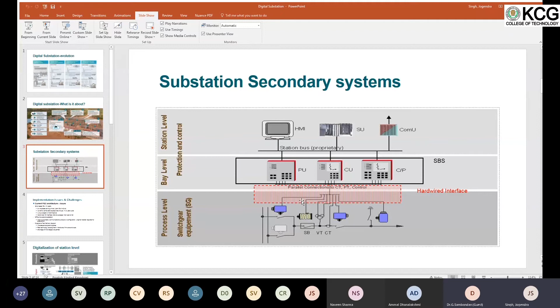No, it can be converted like this. If you see this example, the substation secondary system can be converted using a merging unit, like a merge switch box. You convert all the old CTs and wiring, install a merging unit or transducer on the wiring, and the merging unit will convert the analog signal to digital signals.